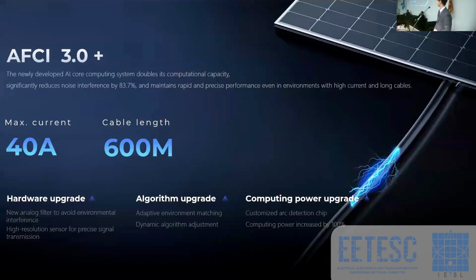Okay, here's the new release, the AFCI 3+ from Sungrow. As you can find from this slide, we have pushed the safety boundary to a new level. It now supports up to 40 ampere max current per MPPT and 600 meters cable length, making it a perfect choice for the largest C&I systems. And also for the sites where the grid connection point is close to the inverter, but the PV panels are located far away on distant rooftops or some remote ground areas. So that's the point.